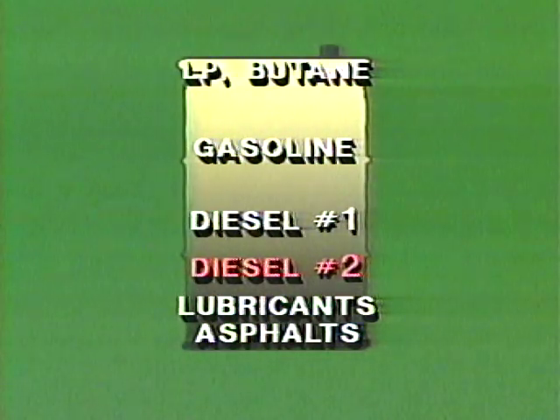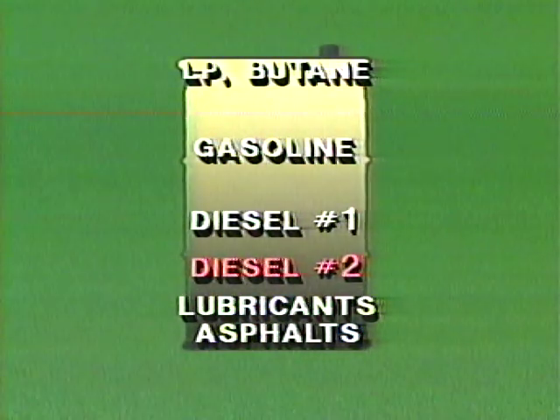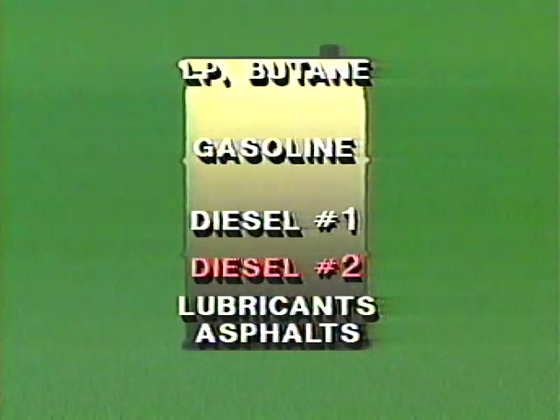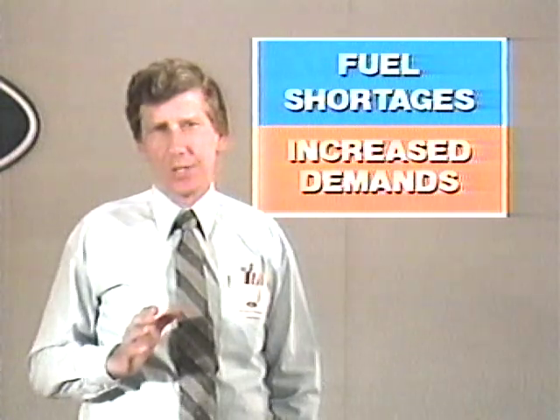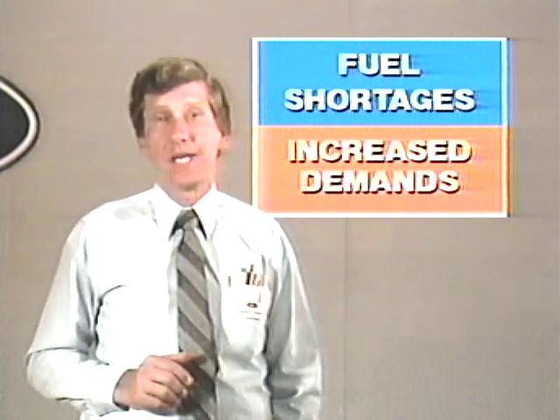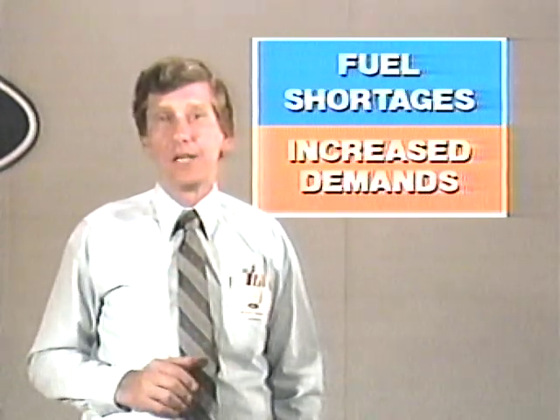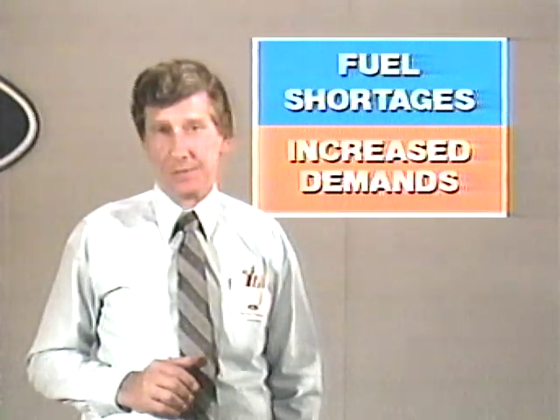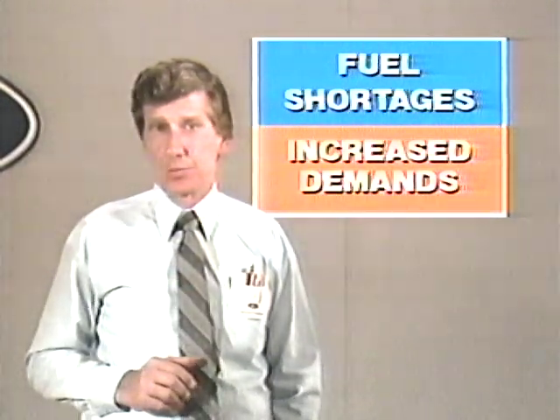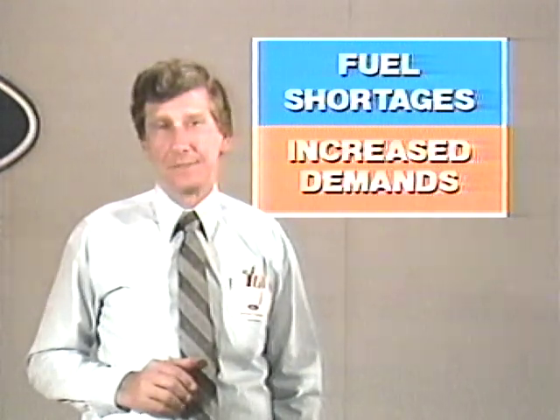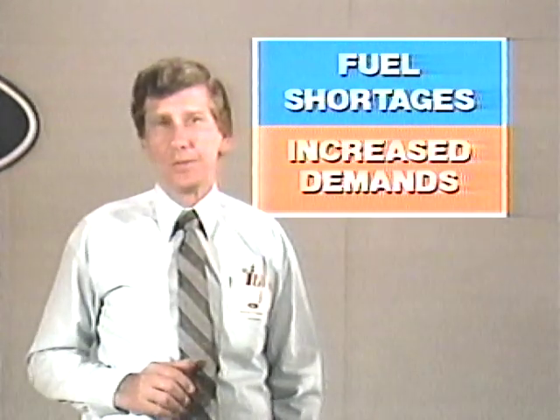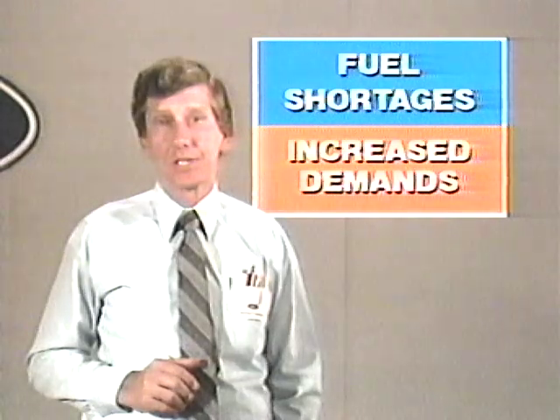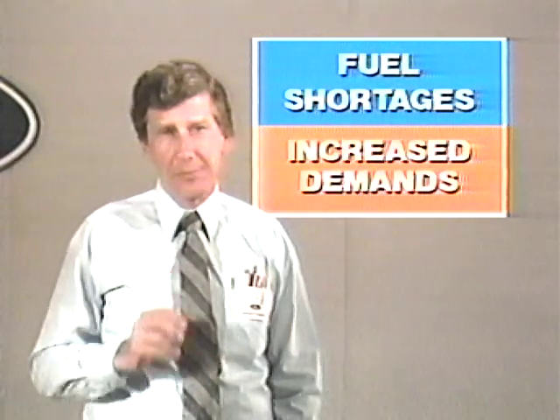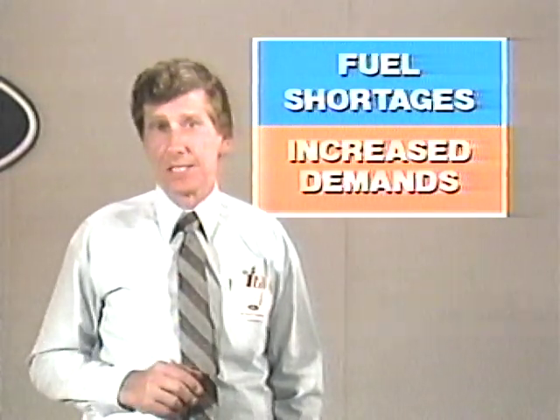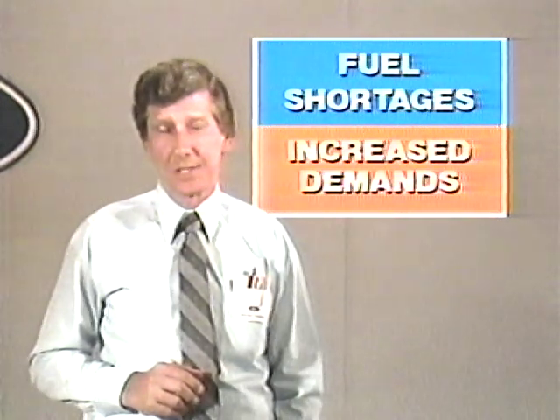Inherent in the lower quality fuel are lower cetane ratings, higher sulfur content, a higher cloud point, and greater water retention. In short, the fuel shortages over the past decade have increased the demand for the #1 band of diesel fuel. Increasing demand has robbed #2 fuel of its quality, and the use of lower quality fuel leads to more diesel fuel system concerns than ever. That means greater care must be taken in the cleaning and maintenance of diesel fuel systems.